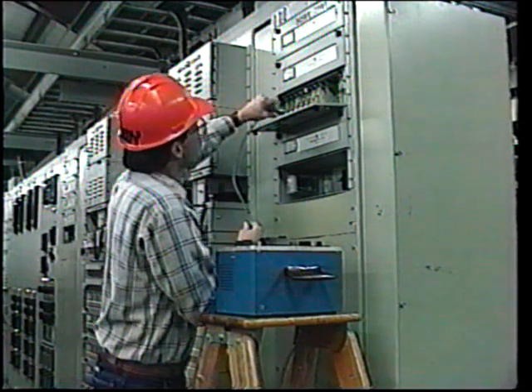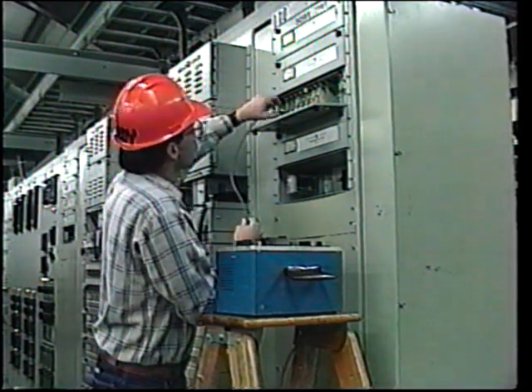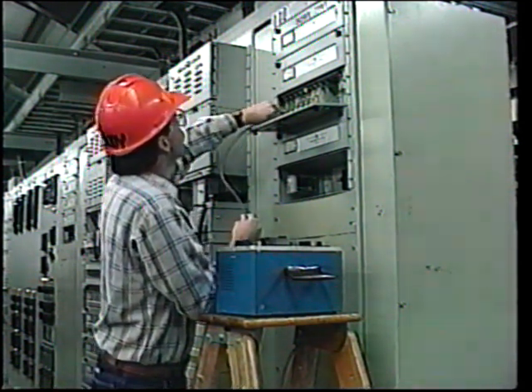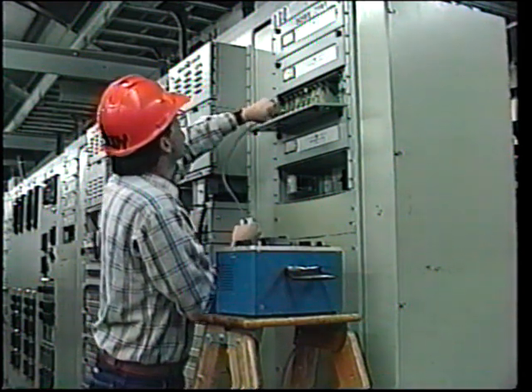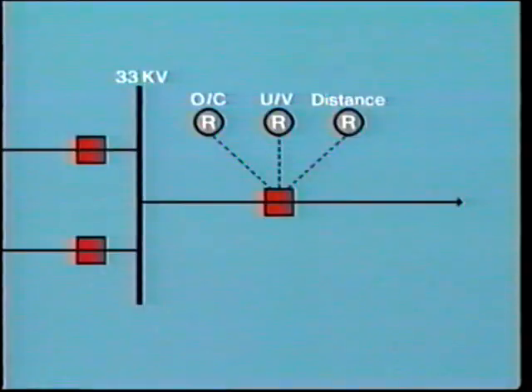This enables the technician to remove one channel at a time for testing, while the line remains in service protected by the single channel. On lower voltage systems where duplicate protection is not provided, we have to rely upon alternate protection to clear any fault while we disconnect one relay at a time for testing. In fact, the ability to perform in-service testing should be taken into consideration during the design of the system protection.